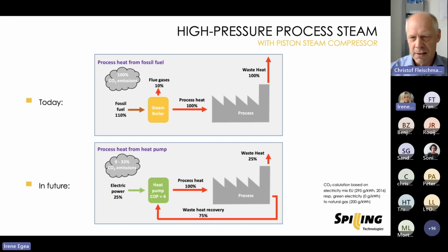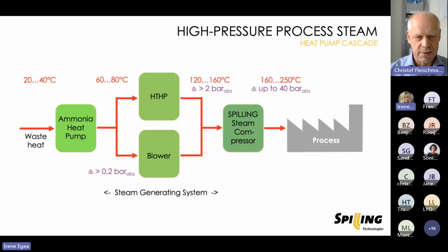Now these industrial heat pumps, which are in the market or which are coming up, can be characterized according to the temperature level where they are operating, like Benjamin's slide also has shown. In the next slide, I would go a little more into these different temperature ranges. From our point of view, here is a cascade of different technologies shown in their temperature characteristic: the source side, what is going into a heat pump, and the sink side, what is coming out of the heat pump.